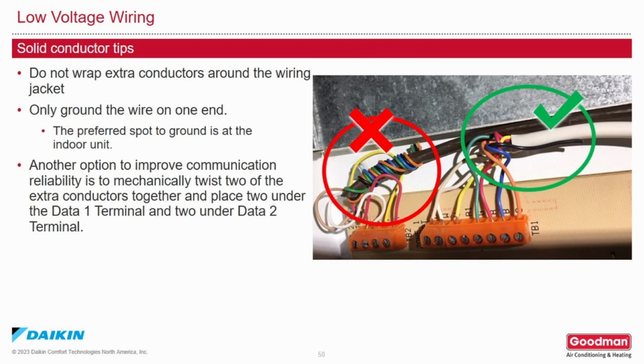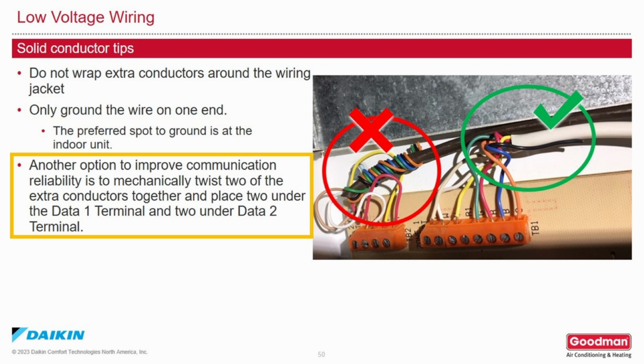If you are using multi-conductor solid core thermostat wire, do not wrap the extra conductors around the jacket like you would with the spare wires on a conventional system. Ground only one end of the wire, and the preferred grounding spot for that would be the indoor unit. Another option to improve communication reliability is to twist 2 of the extra conductors together. Place 2 of them under data terminal 1 and 2 of them under data terminal 2. 18 gauge 2-conductor stranded shielded cable may be a better choice for a communication circuit.